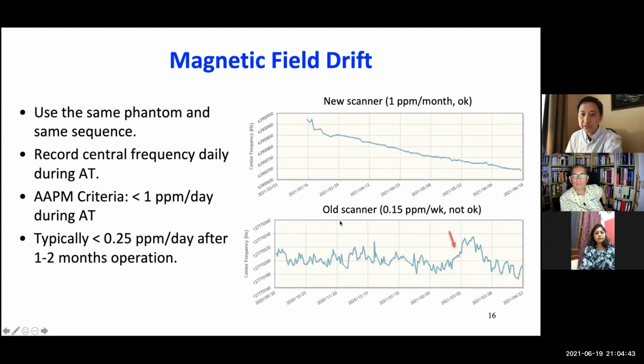Here I'm showing you an old scanner on the lower part, from September of last year. It has been very stable, but recently, early March, the central frequency started to increase. If we look at the number, it's only 0.15 ppm per week. Still within the AAPM recommendation. However, we think this is not okay because the scanner has been stable for so long, and this is a very consistent change. So we did call the service, and the service came in and found a pressure increase.